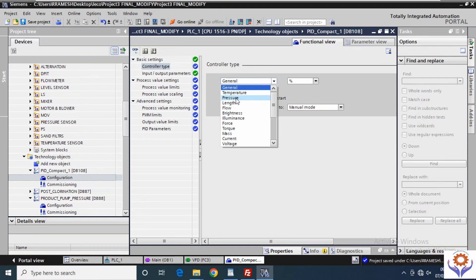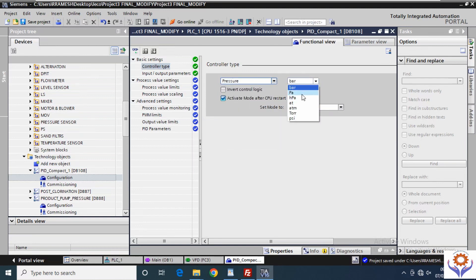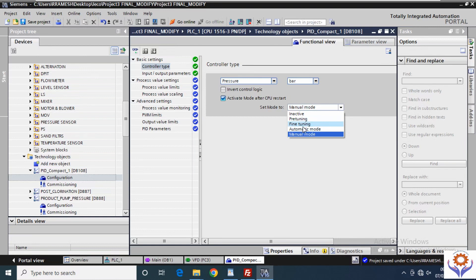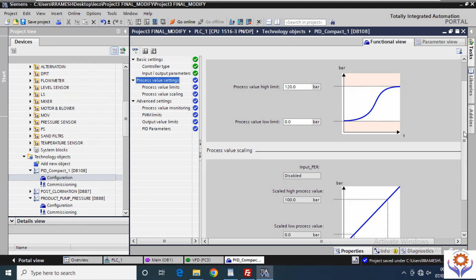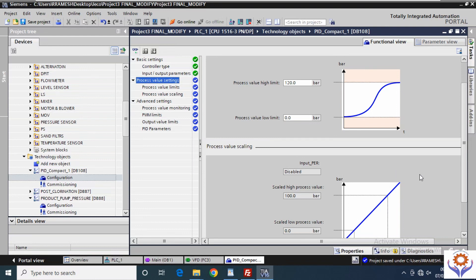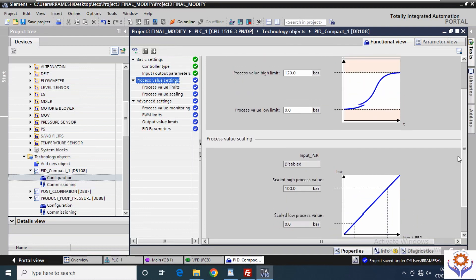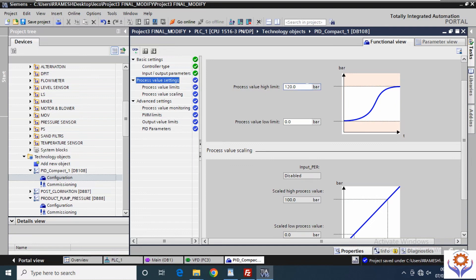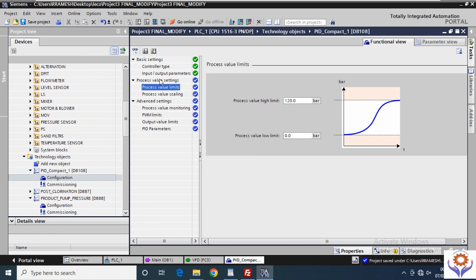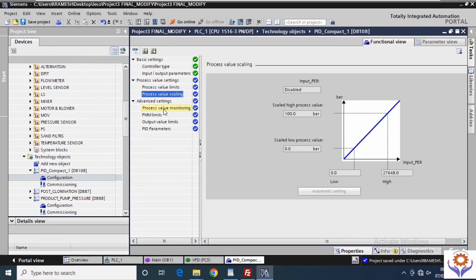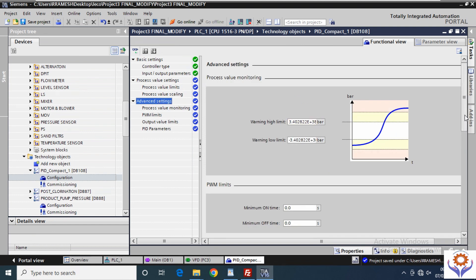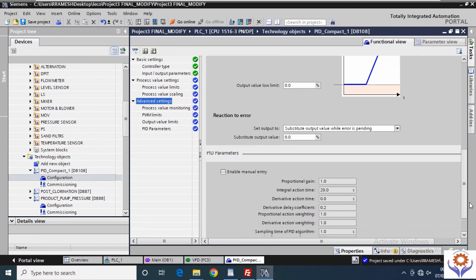For my case, I will select Pressure as the controller type. The units will populate automatically with the relevant types. You have many Set Mode options as well. In the Process Value Settings, you can see the low range and high range — you need to set your limits. In Process Value Scaling, you can set the scaling. I will keep everything as default for now. In Value Limit settings, you have the same functions. In Advanced Settings, you can give warning limits, minimum and maximum limits.